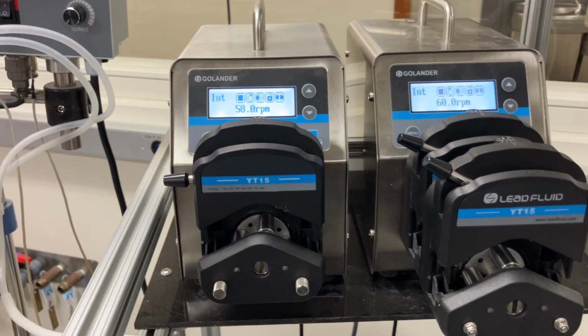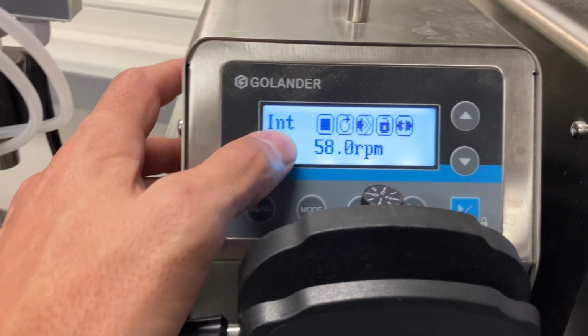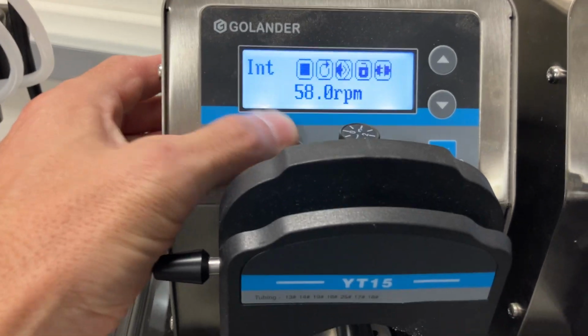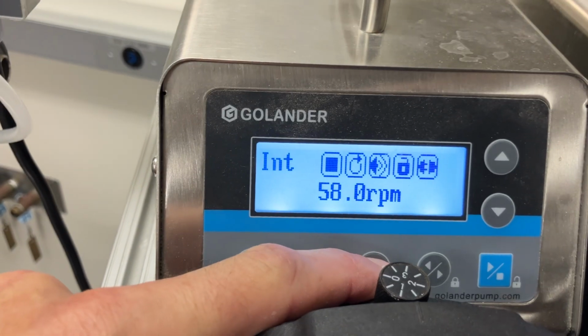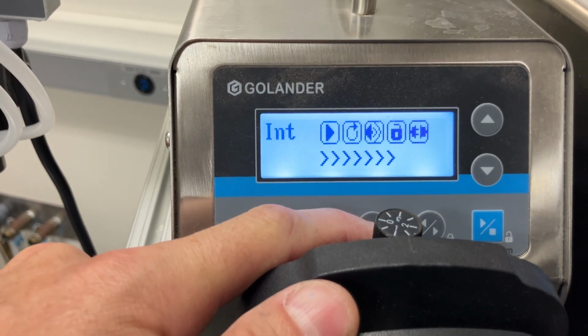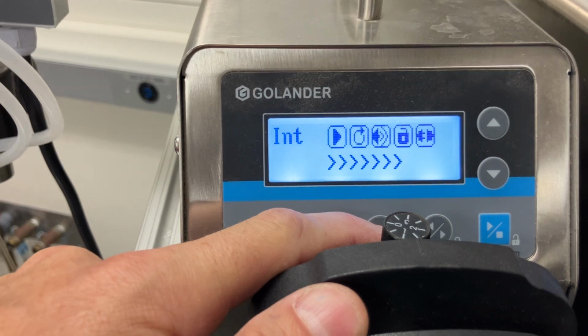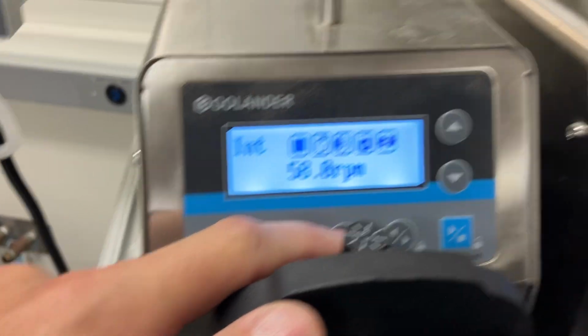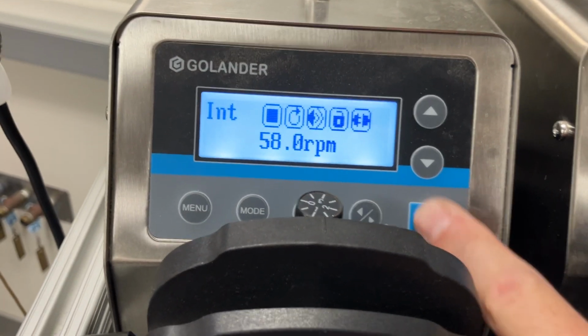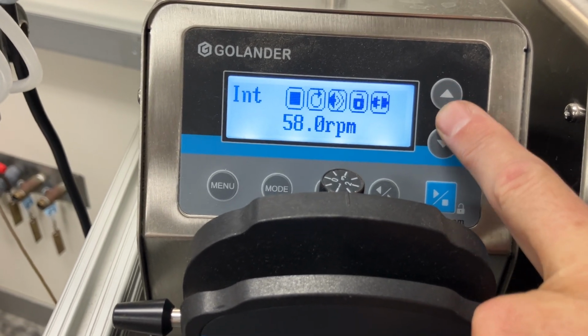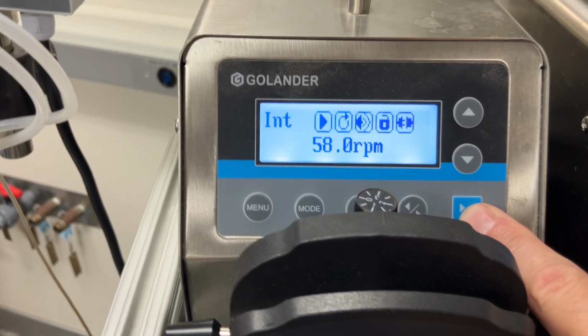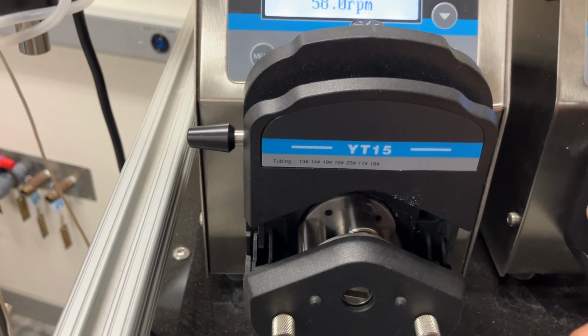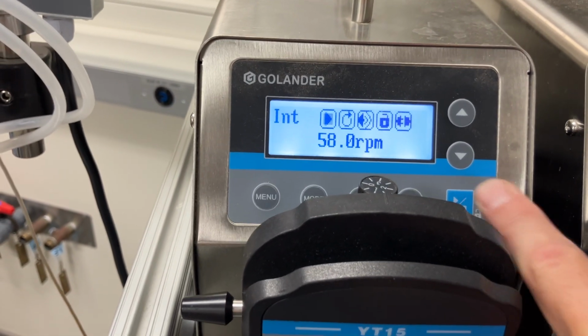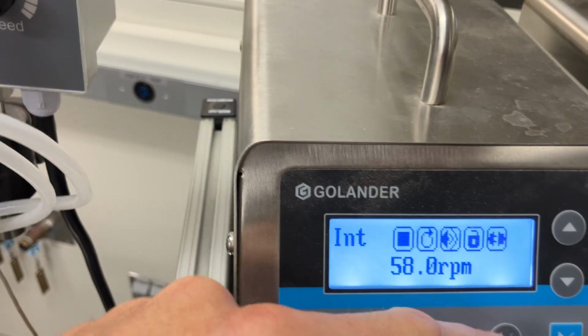You can pump into and out of the reactor with these peristaltic pumps. It should read int on the left. If it doesn't, you can hit the mode button, and here you can turn it so it's rotating as fast as possible to move material quickly, temporarily. Hit that again, turn off, and then the play button, after you've set the RPM that you desire, can be used to just turn it on, and it will run at that rate. You can also change the direction with this button here.